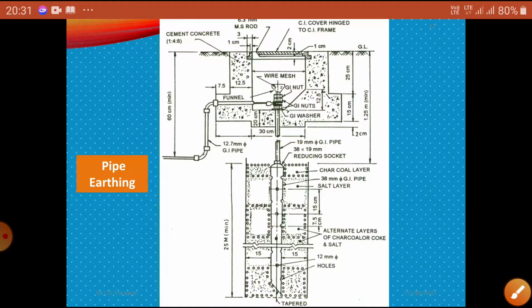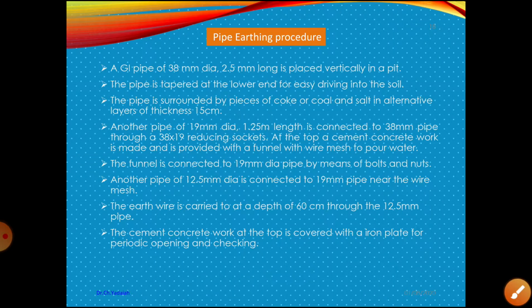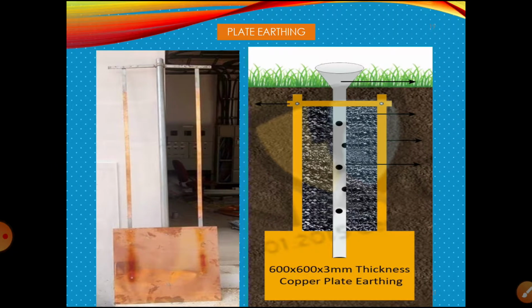So instead of a GI pipe length, I can increase the contact area using a 60 centimeter copper plate. That's the only difference here, so place the copper plate here instead. Everything else is similar. This is the copper plate, generally 60 centimeters by 60 centimeters, 3 mm thickness, placed as the earth plate.